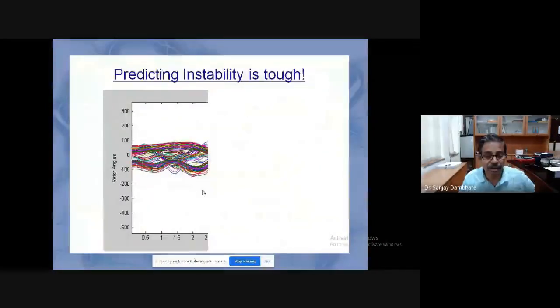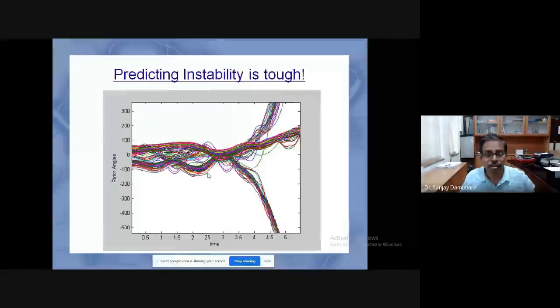So we have just simulated the system of the western region, wherein we have Madhya Pradesh, Gujarat, Maharashtra, Chhattisgarh, and Goa for the transient stability studies, and then we created the fault on one of the transmission lines passing to Dhulia, and you can see that the system is stable in this period. But after that solid fault at the Dhulia bus, the system has trifurcated into 3 zones. So it has trifurcated into 3 coherent groups.